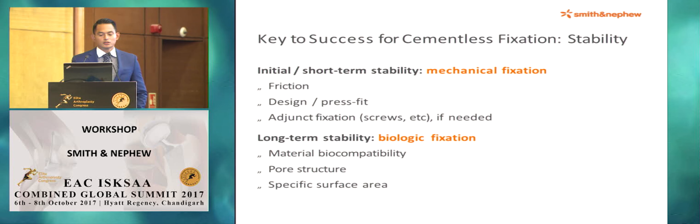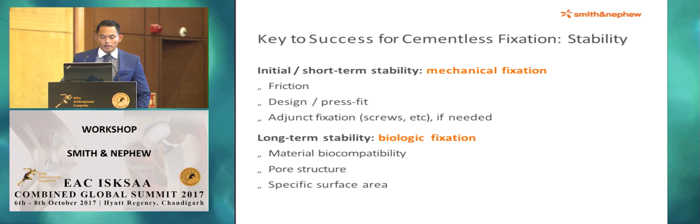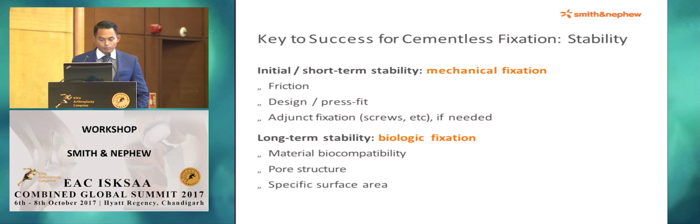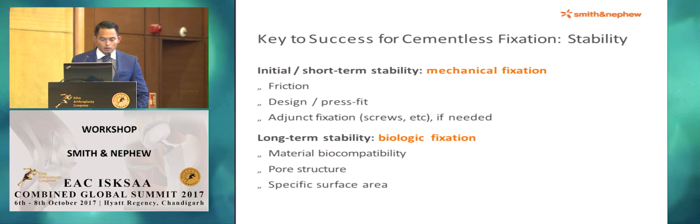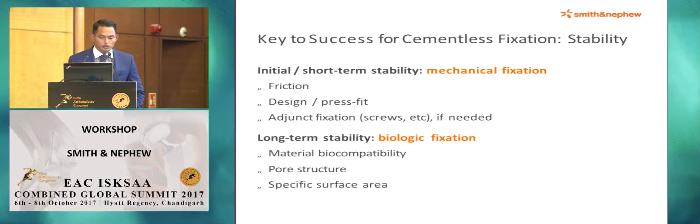The keys to successful cementless fixation: number one is stability. You want initial short-term stability with mechanical fixation, as biologic fixation obviously takes some time — a good coefficient of friction, good design with appropriate press fit, and adjunct fixation with screws if needed. Your long-term stability relies on biologic fixation — you want a material that is biocompatible, with a good optimal pore structure and optimal specific surface area.